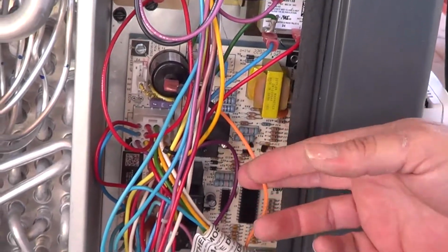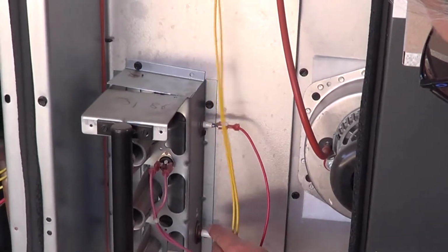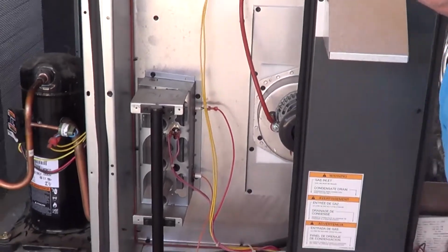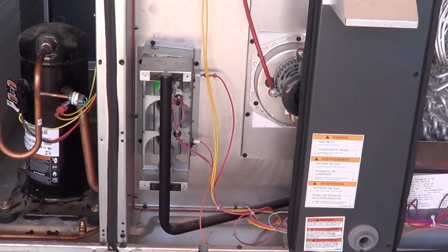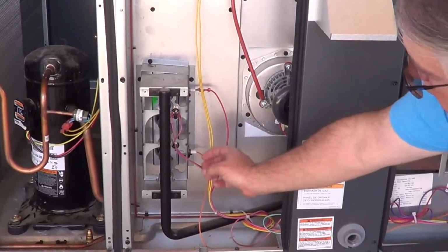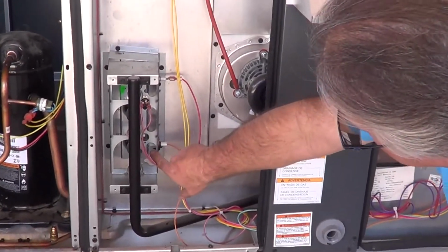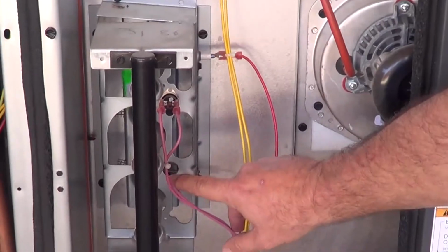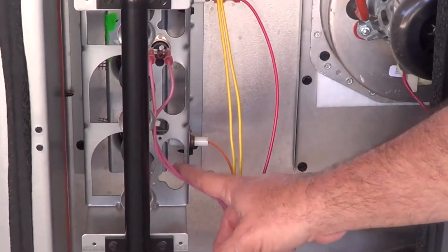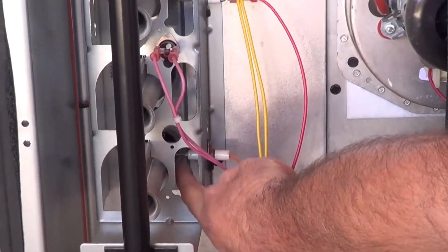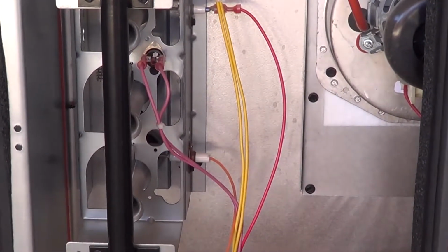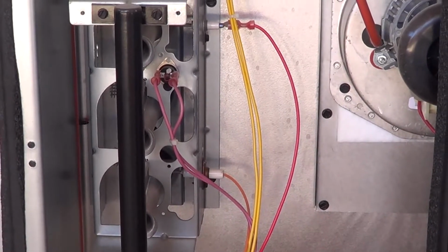The AC current is sent through the orange wire here over to the furnace side, over to the spark emitter. The spark emitter acts just like the spark plug inside of a car engine and creates an arc of electricity between the probe that is in there and the burner. So there's actually a high voltage arc of electricity that will jump from the probe that's inside there over to the burner to ignite the natural gas.